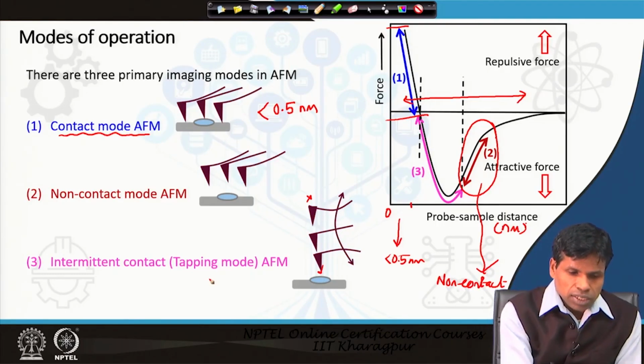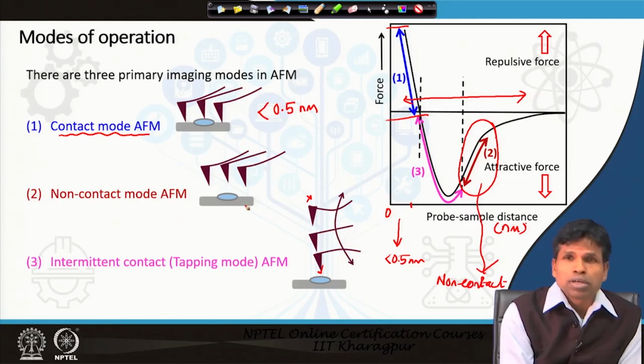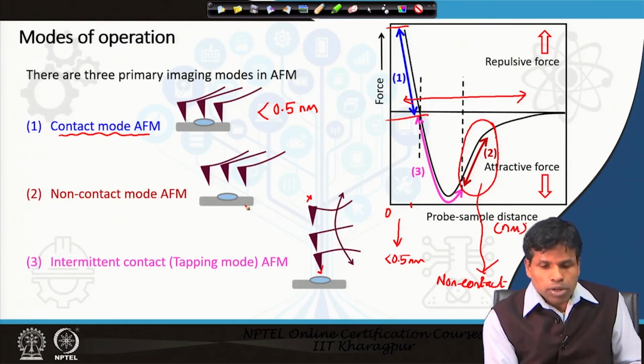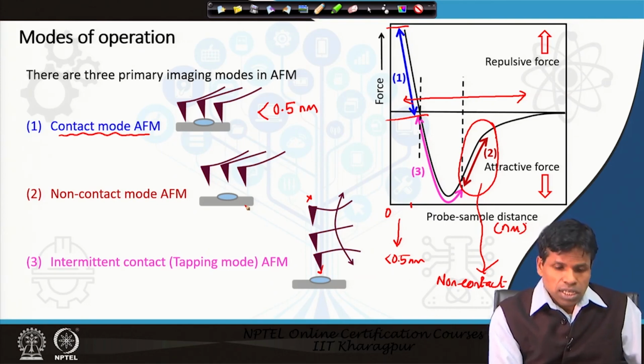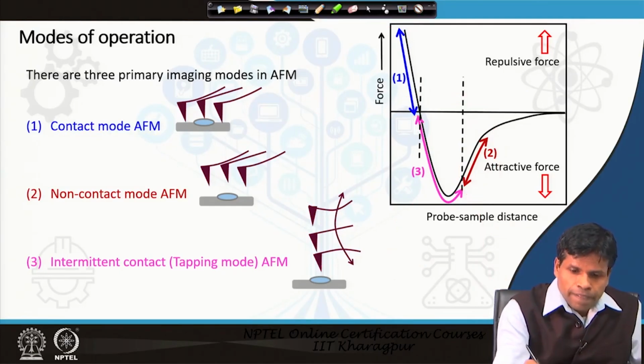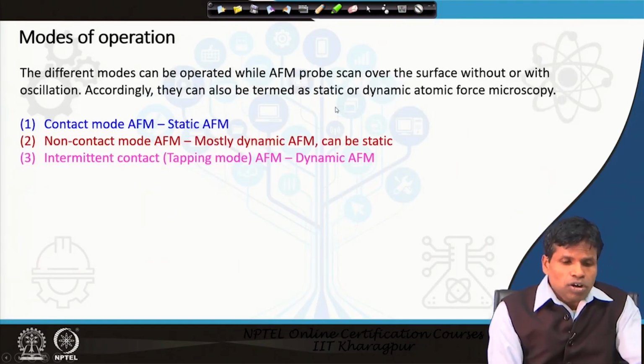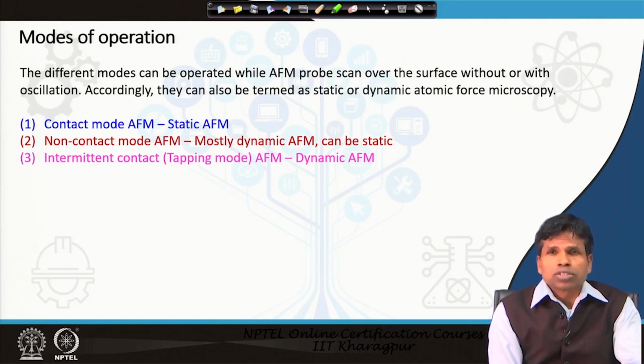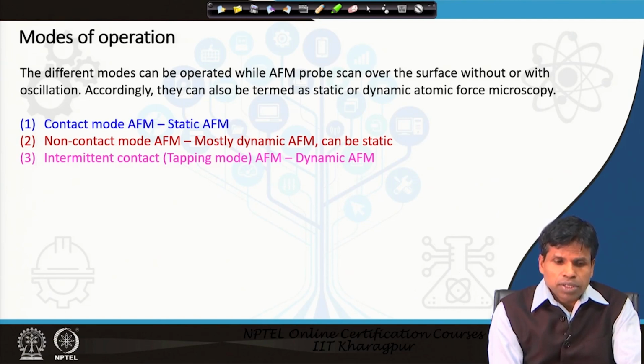And here the non-contact mode is when tip and sample are far away from each other. Not far away means it is about more than 2 nanometer, and where attractive force predominates. Going into a little more detail, we can also differentiate these modes into two different categories, that is called static atomic force microscopic measurement, and another is called dynamic atomic force microscopic measurements.